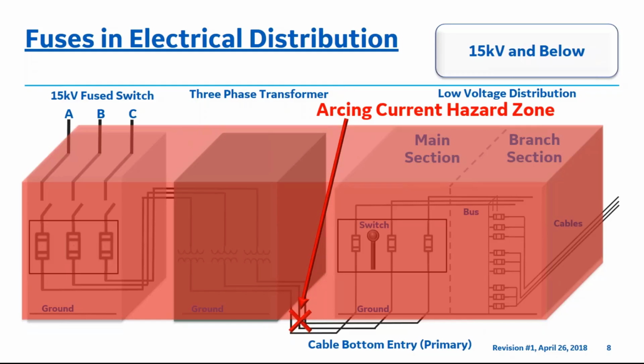I'm illustrating a separation between these sections to help show where arcing faults can occur. But it is commercially possible to close couple these sections together if space constraints are present. If you do have a close coupled 15 kV fuse switch substation application, changing the length of the cables changes the impedance of the unit substation, but the arc flash zone will affect the entire substation, just like the first example. If an arcing fault occurs on the close coupled unit substation, it would significantly and immediately affect the entire substation with the large arc flash zone. But for this illustration, I'm showing a separation.